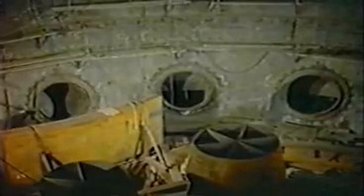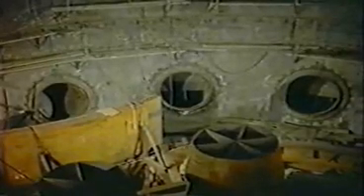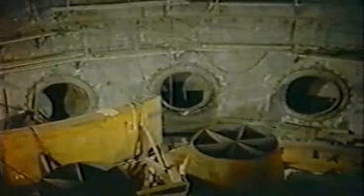These inlet apertures in the vessel allow the carbon dioxide coolant gas to recirculate through the core after the gas has given off its heat to the boiler tubing. Each boiler has its own circuit and gas circulator. The ducting, which is 5 feet in diameter, passes through the biological shielding to connect to the outlet end of the circulator.